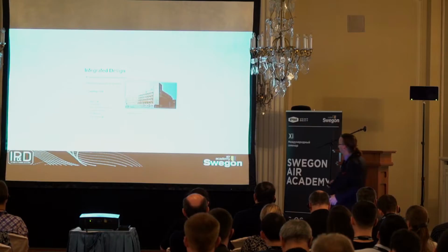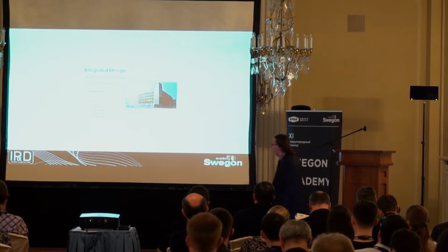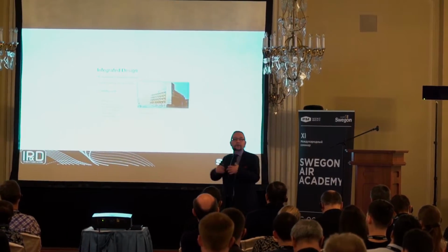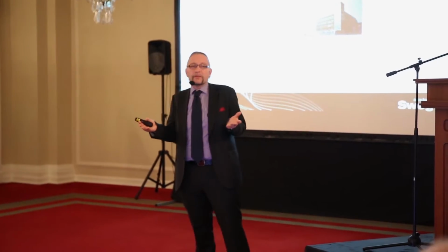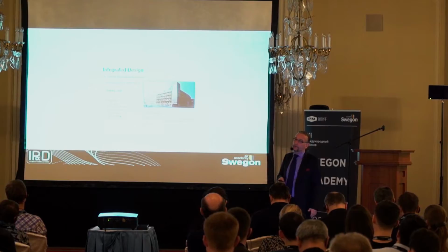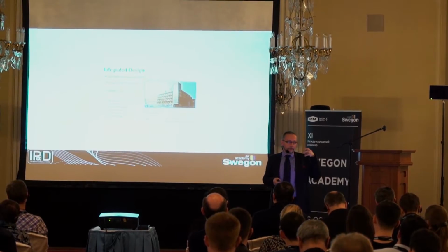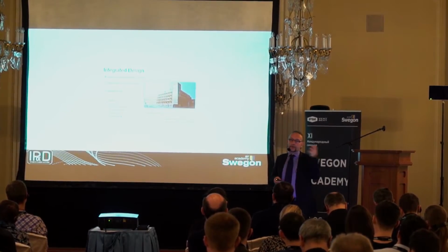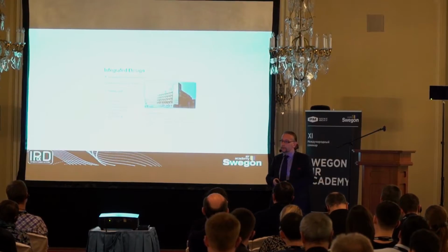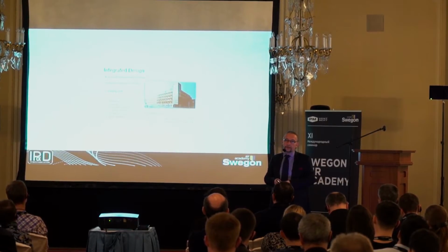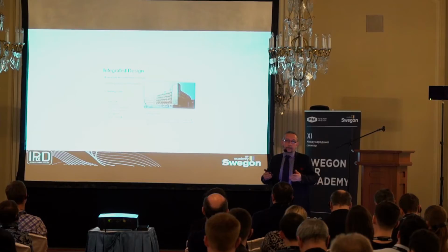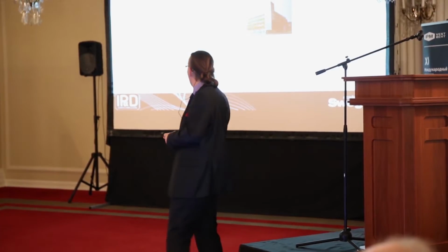Take the quality of glass as an example. In wintertime, a good U value is nice, but the U value doesn't matter much in summertime. In summer, it's the solar factor that matters—how much solar thermal energy you keep outside. You don't want more than 40% of that energy getting into the building, otherwise you raise the amount of cooling needed, and that costs a lot of money.